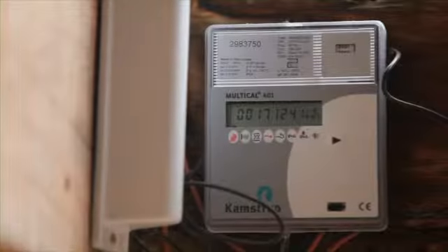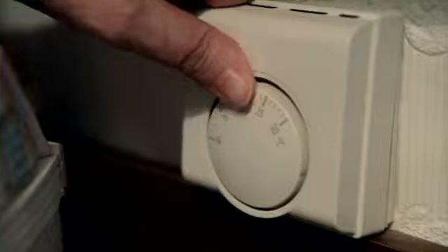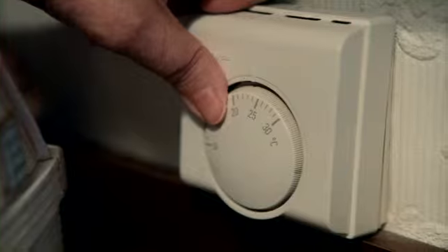Temperature measurement of the flow and return lines plus a flow meter together form a heat meter. This allows the actual heat usage within each building or even apartment to be separately measured. More modern systems, including biomass district heating systems, tend to use such a heat metering system, as it means that each building or home can be accurately billed for the kilowatt hours of heat they've used. This is preferable to applying a flat rate charge where the total energy consumption is divided by the number of buildings supplied. This was the common method in old coal and oil systems and tends to encourage wasteful use of heat.